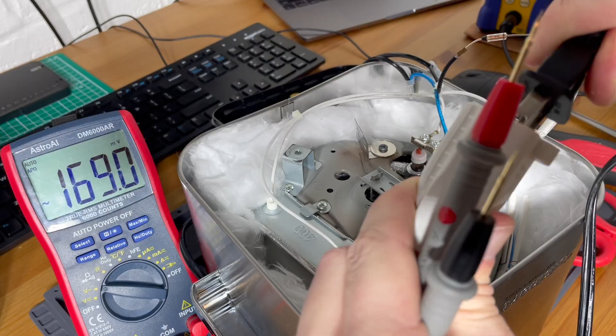So I'm going to confirm that with the meter. Let me put this back, set the meter to AC volts again, and plug the unit back in. I'll put one lead on that neutral where it was before, and test the incoming side of the fuse—I expect to see good voltage here. And we do see 122 volts. Then on the other side of the fuse I expect to see nothing, and that's what we see.